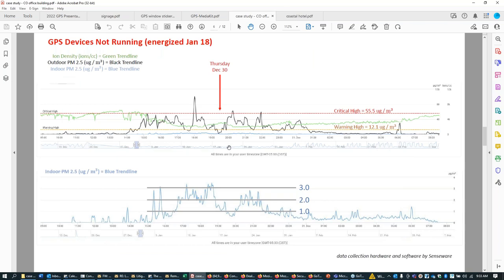What we were able to show the owner was what was taking place inside the building. I've got it charted on the same chart up here, but you really can't see it because of the y-axis scaling. So I put it down here with the same time window. And here's what we measured inside the building during this multi-hour wildfire event. The building engineer confirmed he did not turn off outside air. The building continued to run as normal. The building was lightly occupied. And what you see here is that this building had MERV 13 filters, and the inside air quality, the PM 2.5 trend, stayed below about 3 micrograms per cubic meter.